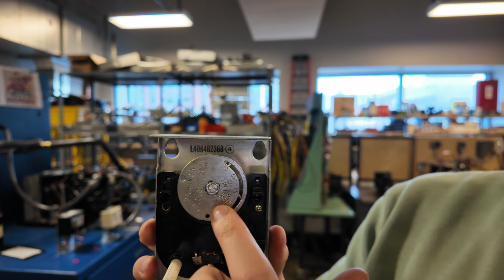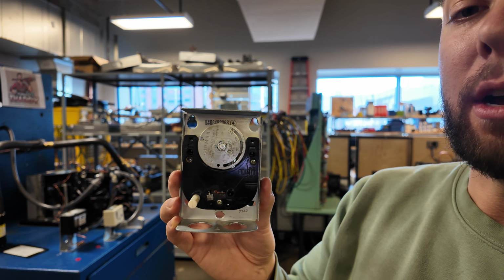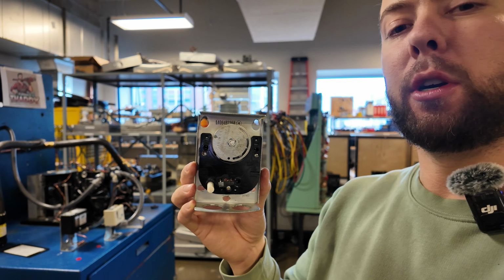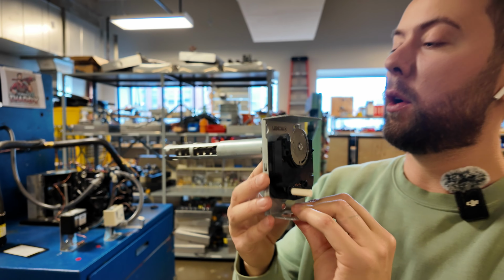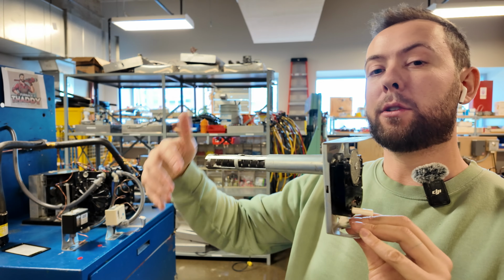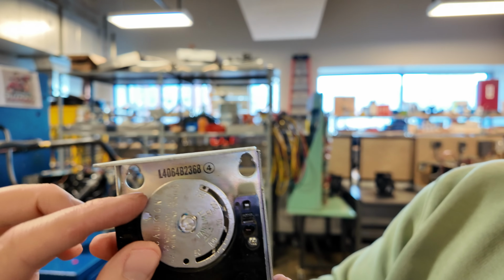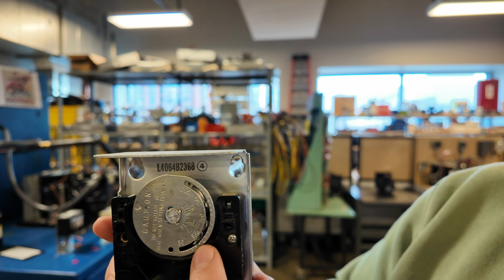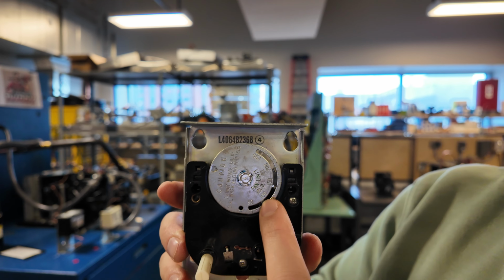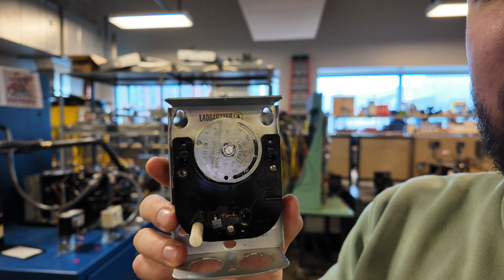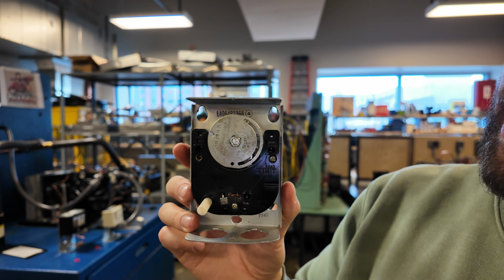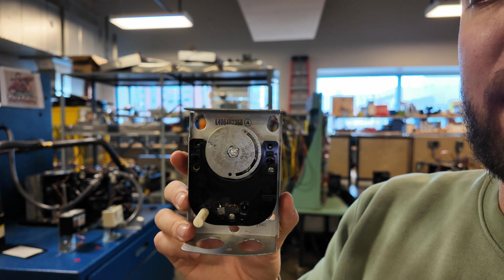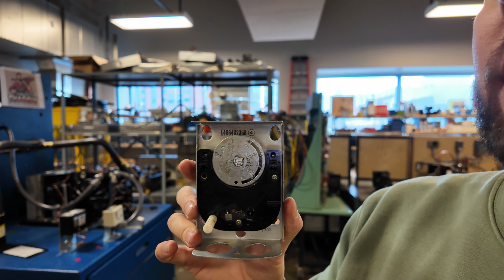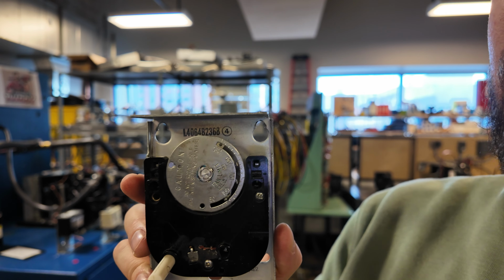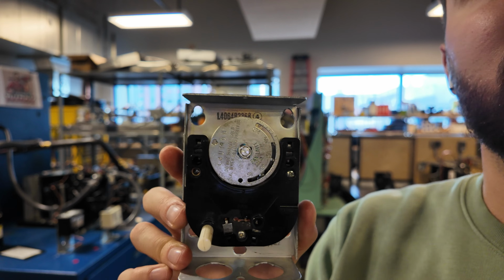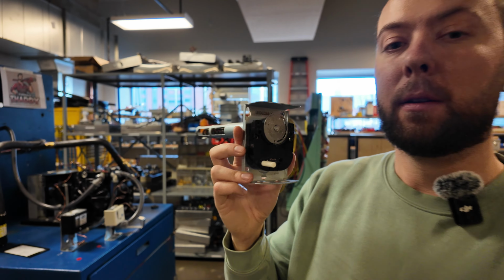So how the cutout works is, now we've hit temperature, so the gas valve turns off. We're good with that? Room temperature rose, we hit temperature, gas valve turns off. And now the blower will be cooling this bimetal strip and also the heat exchanger. And as it cools, it's going to keep turning. Once it cools to our cut-out set point, which we set at roughly 90 degrees Fahrenheit, it will de-energize the blower motor, and the unit will go into standby. It's really important not to set the cutout too high, because if you do, your heat exchanger is still going to be very warm, and you're actually going to waste energy. We want to remove as much heat from the heat exchanger as we can, to get that last little bit of heat into the space instead of wasting it, in my opinion. So yeah, it's the basics of a fan control.